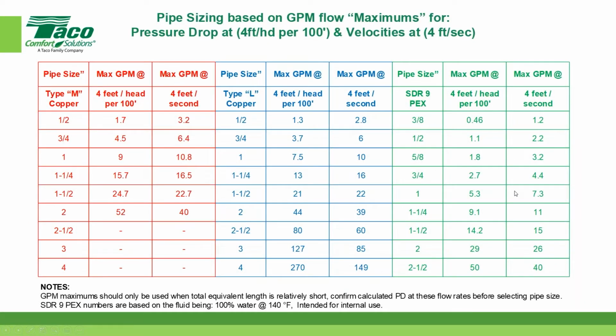Here's another version of that same thing. It's a maximum velocities chart, but over here in red, I have type M copper. Here in blue, I have type L copper. Over here in green, I have SDR9 PEX. SDR9 is our standard dimension ratio. So anything that we're using nowadays in North America tends to be SDR9. That has to do with the wall thickness. Same caveat down here though.